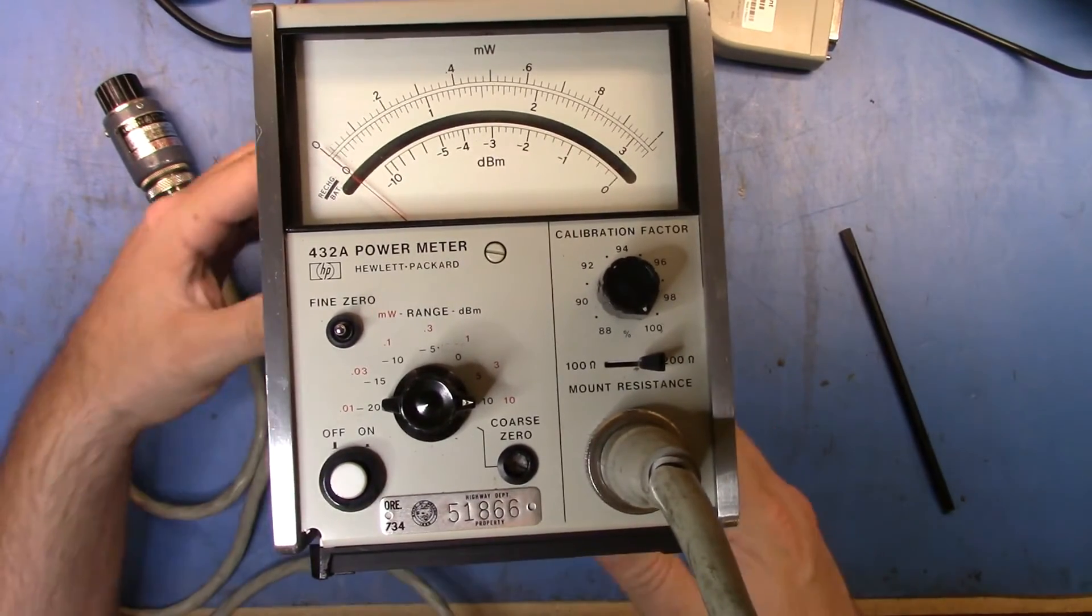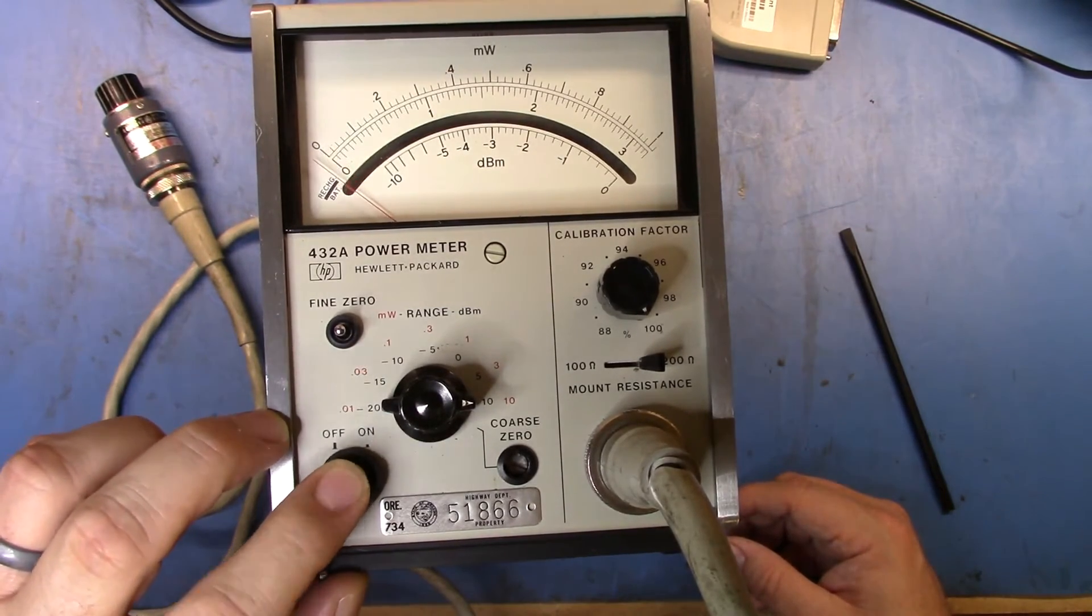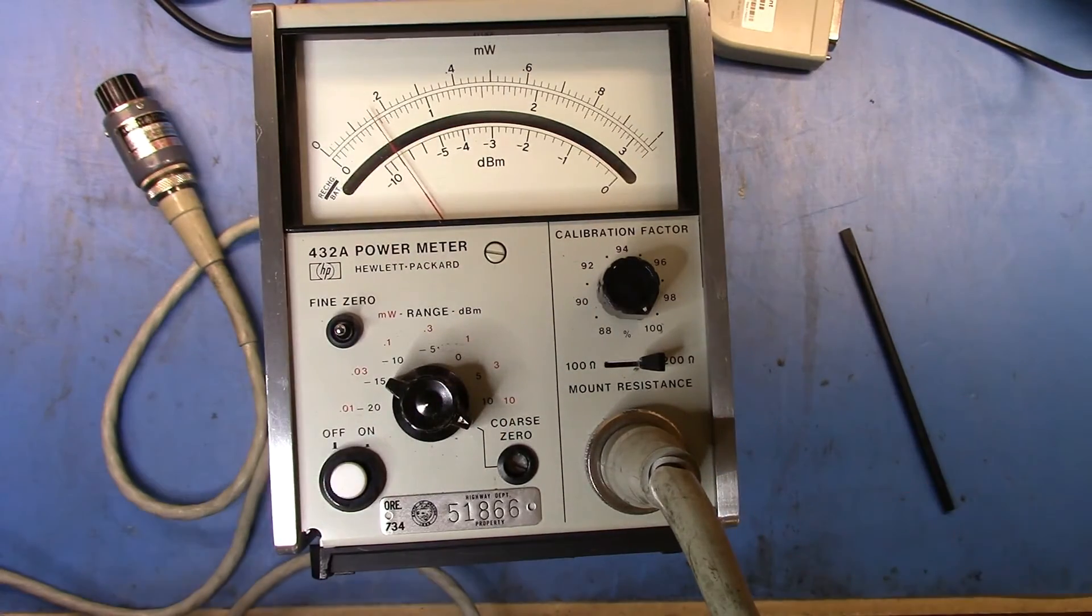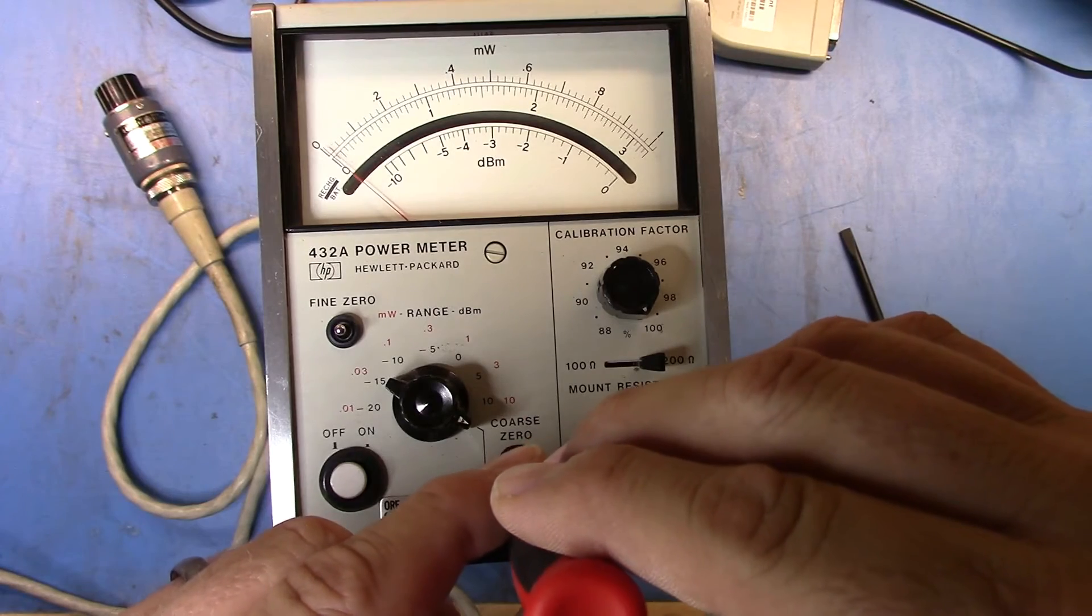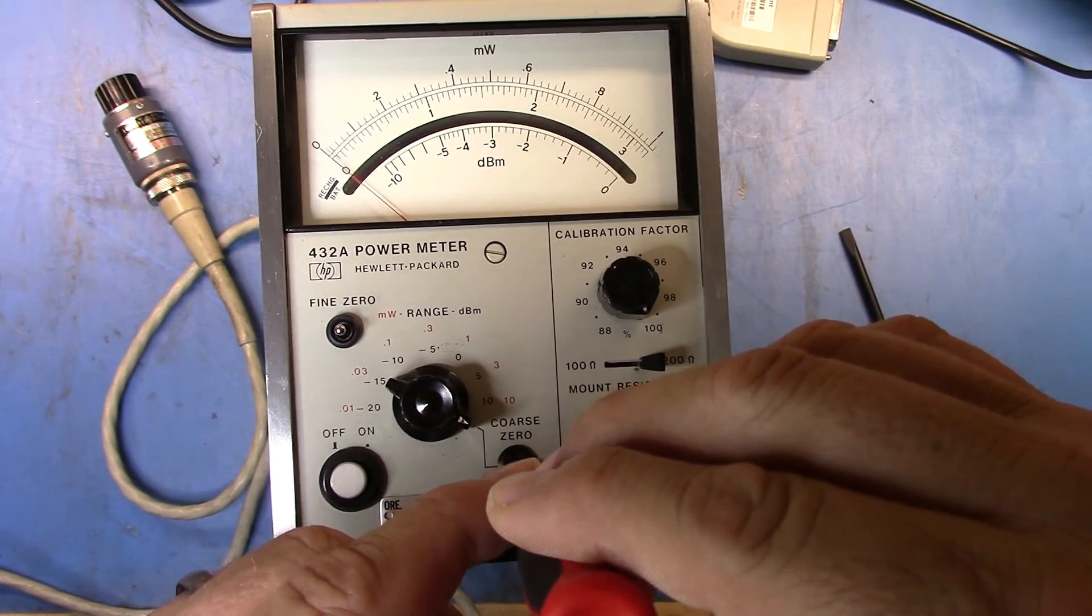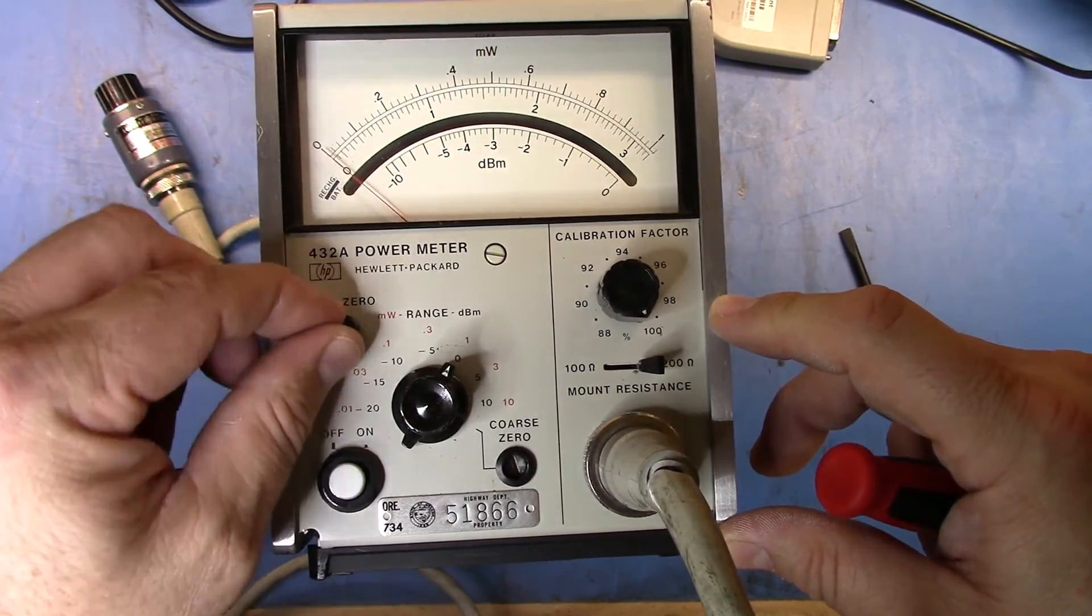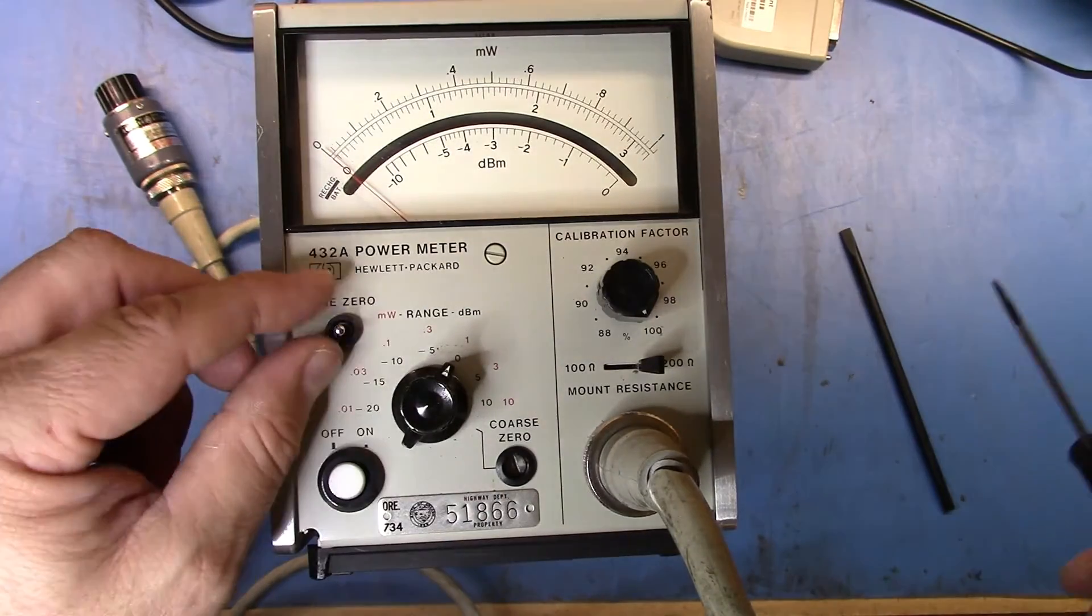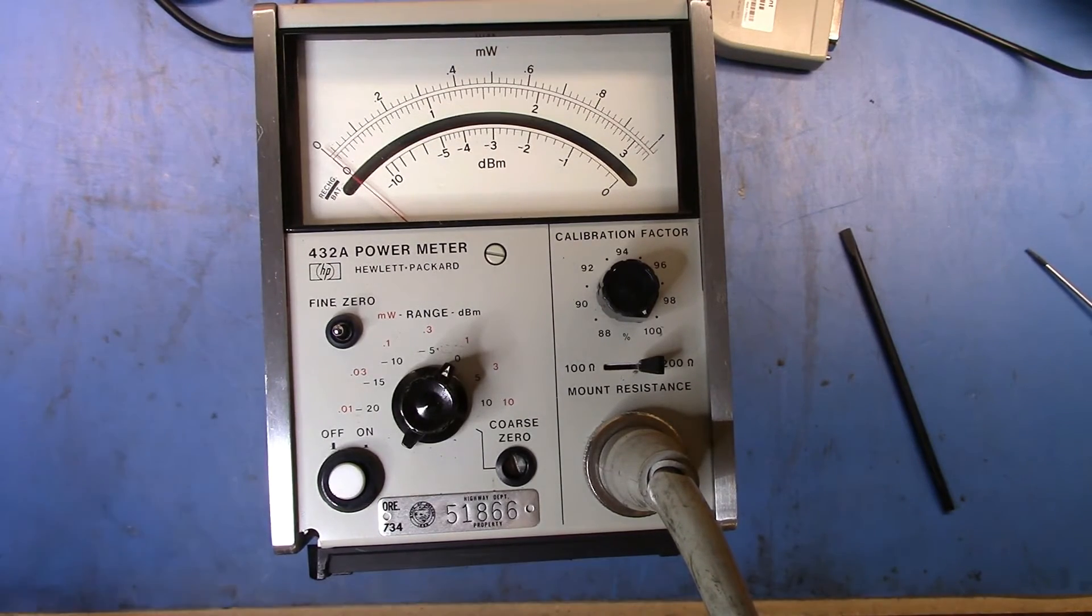Let's turn this on and see what happens. I guess it was on. So now we turn it to coarse zero, and we can zero down the meter to get it in there. Then we set our range and use fine zero to pull that in. Basically, you set the coarse zero, and then at each range change, use fine zero again to zero back in. Now I'm going to connect this to an 8657B.